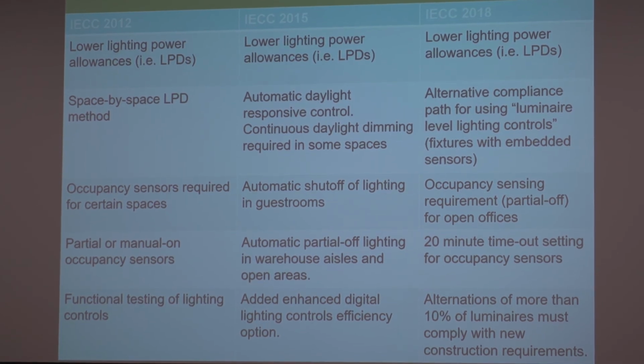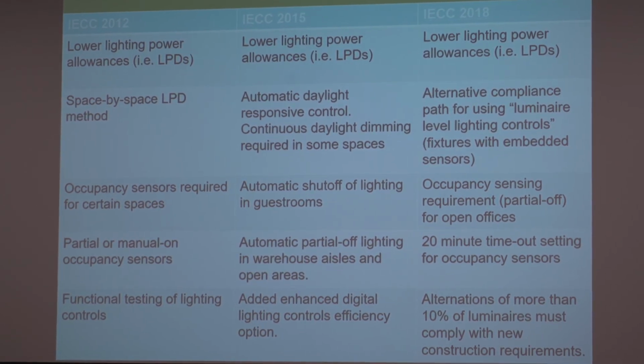Lighting power allowances have gotten lower from the 2009 code, so you'll see that. And then they added the space-by-space lighting power allowance method. Before, with 2009, there was only a whole building lighting power, watts per square foot of lighting that you can use. Now, if you wanted to get a little bit more lighting power, you can do a space-by-space method and break that building down into individual spaces to basically match what ASHRAE does.